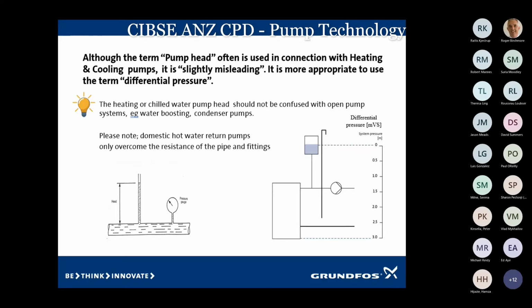In a closed loop system, where it could be chilled water or heating, we don't have to consider the height of the building when we're calculating our head for the pump. All we need to do is calculate the losses through the pipework and through the fittings and any units that we're putting water through. I guess that's the easiest way is to look at it as like a bike tube full of water. And while that water's sitting in the bike tube, it's pressurized in the bike tube, but we need to move that water around.